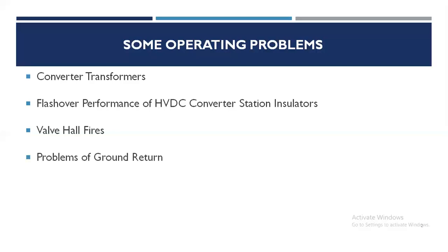Fourth problem is regarding problems of ground return. Although ground return during the monopolar operation cuts down power losses, it can also cause problems with the buried metallic structures and three-phase AC transformers with grounded neutral. The DC current flowing through the ground can enter the neutral and flow through the transformer windings and AC lines. The DC current flowing through the three-phase windings tends to saturate the magnetic cores unequally. The current magnitudes depend on the potential of ground mats where the transformers are located.